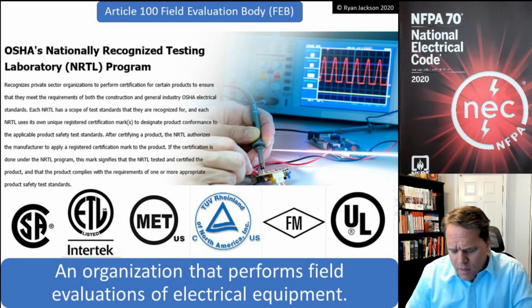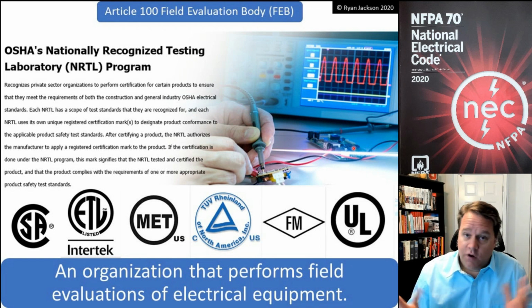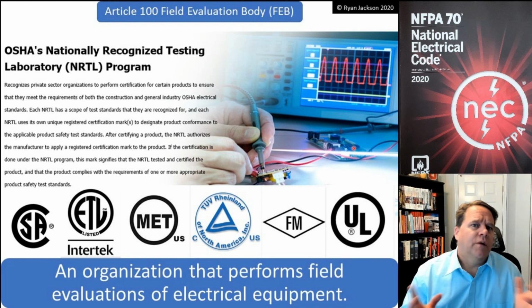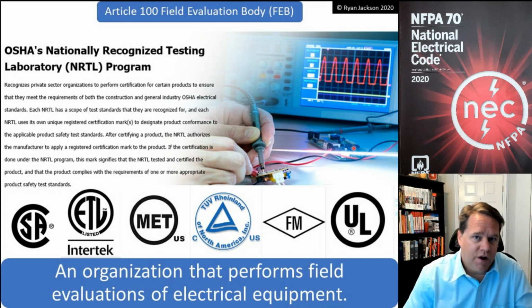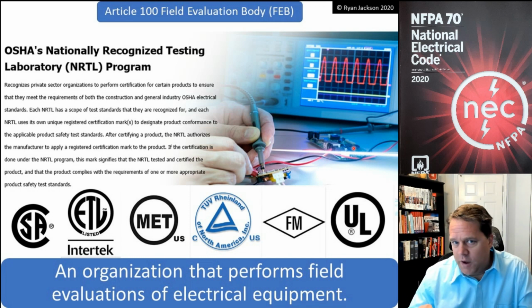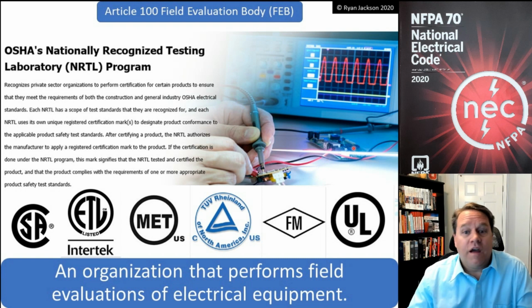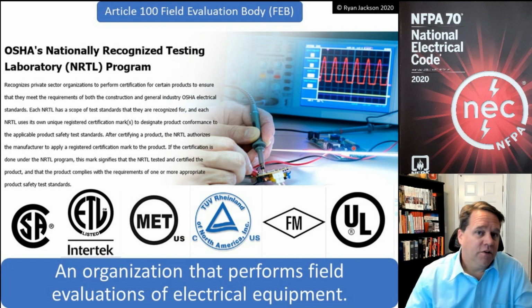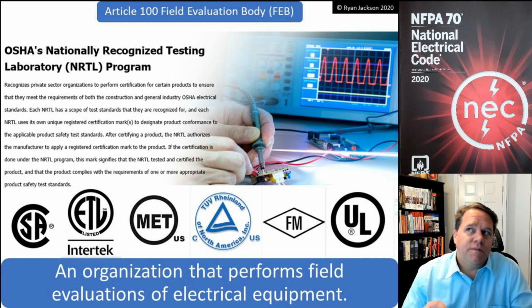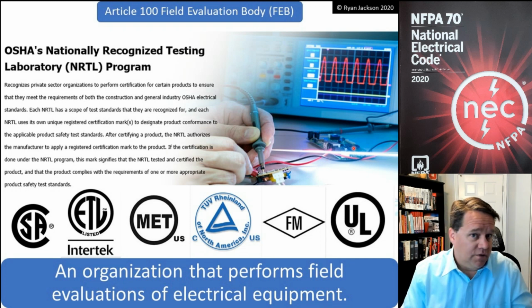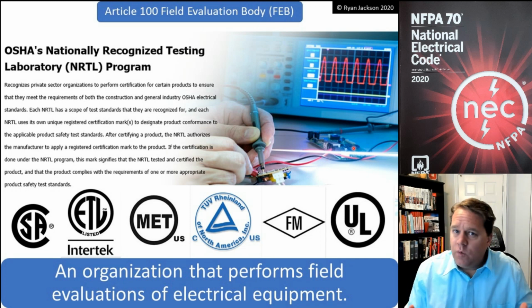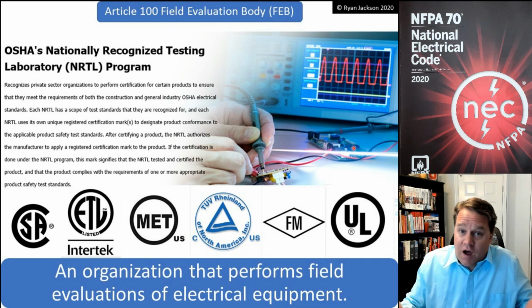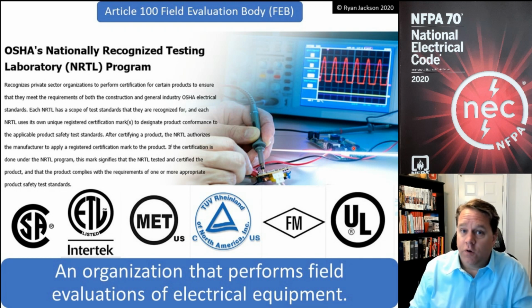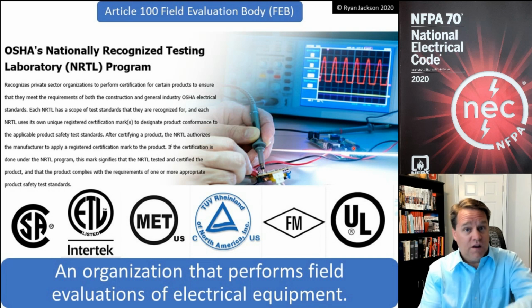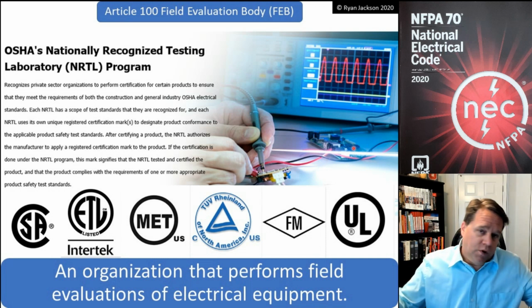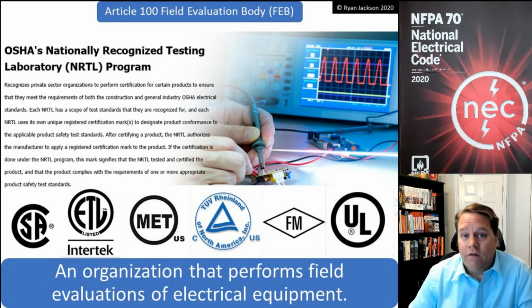Well, listed is listed. There is no equivalent. There's no substitute for listing. Either it's listed or it's not. But most inspectors will consider a field evaluation and a field labeled product to be good enough instead of a listing. Field evaluation and field labeling is not the same as listing. And if your inspector says, the code says listed, it's got to be listed, then your inspector's right, even if you do have a field label.